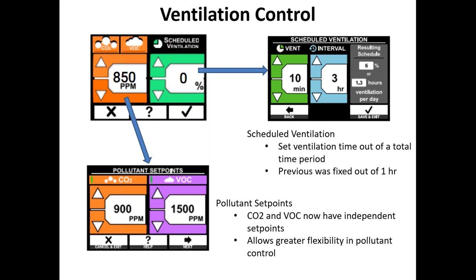So in this case, you could set the CERV to ventilate 10 minutes out of every 3 hour interval, no matter what's going on. So even if your air quality is fine and you don't need ventilation, this just lets you add a base level. This is really how conventional ERVs and HRVs operate on a schedule. So this just lets you set a baseline level of ventilation no matter what.